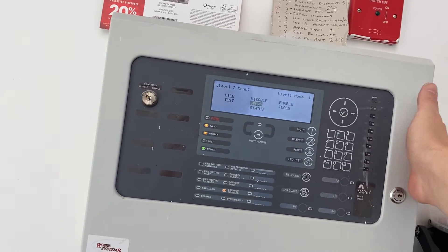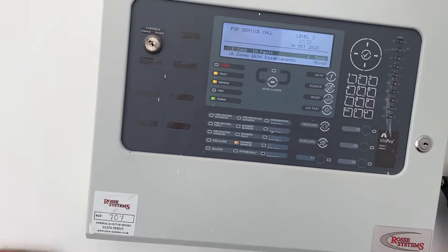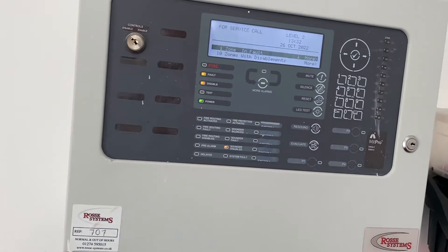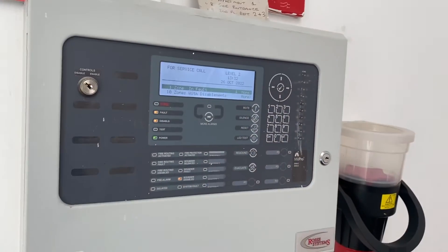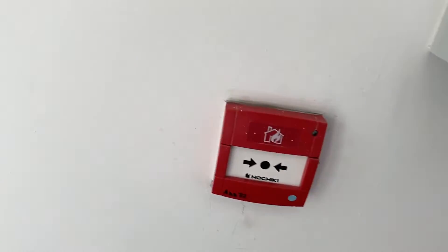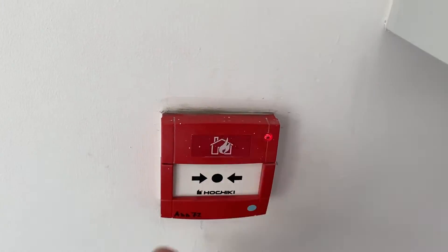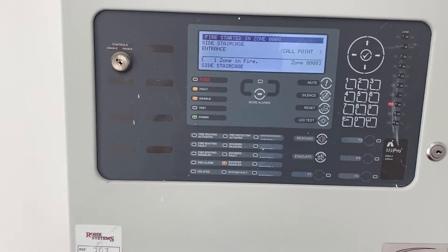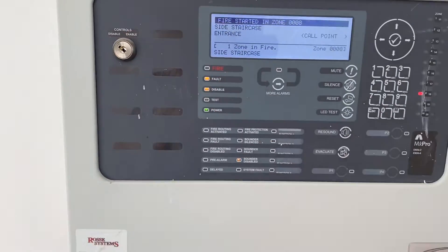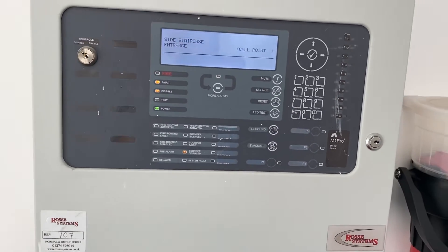Come out of your menu by escaping and then go to status. You can see the zones now have disablements — that's our sounders. Hit the call point for fire again and this time the panel will act as if there was an actual fire, displaying the zone and the fire warning.